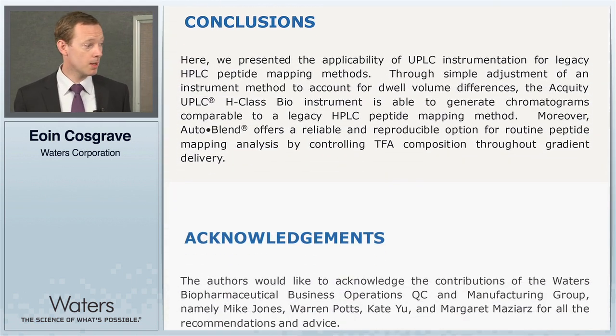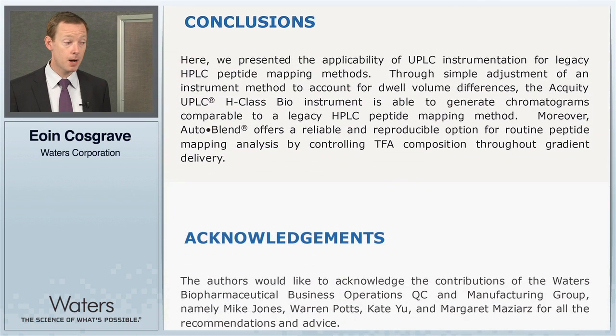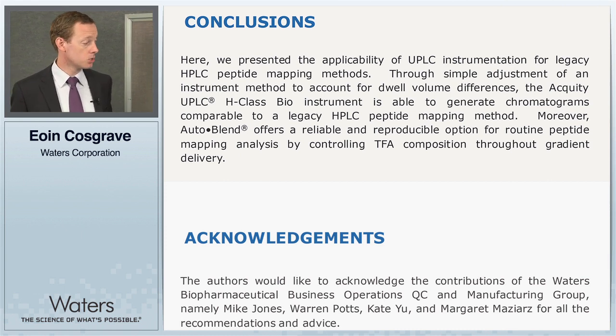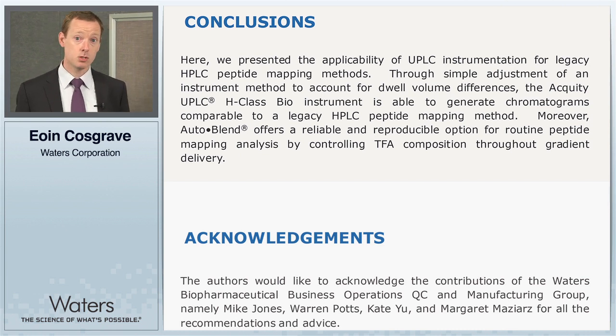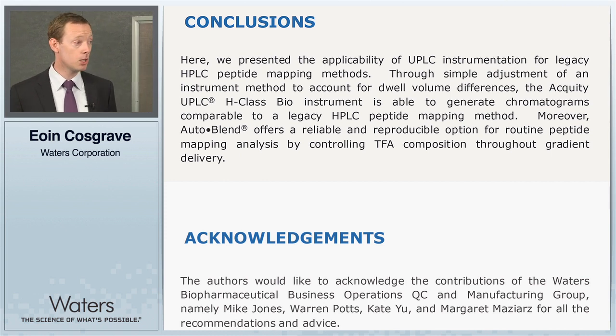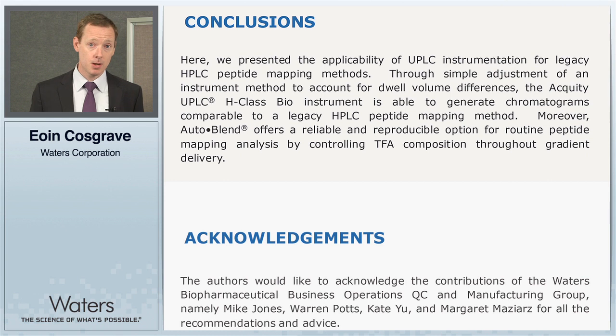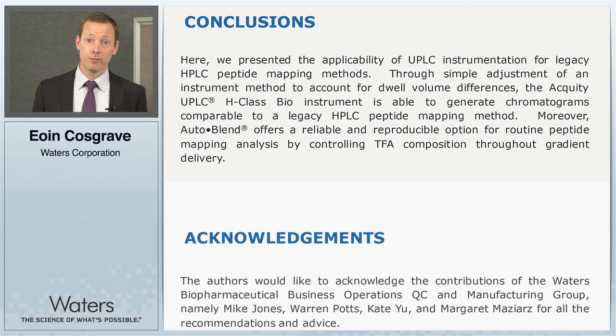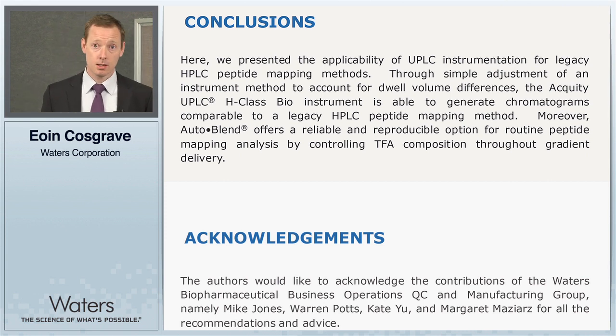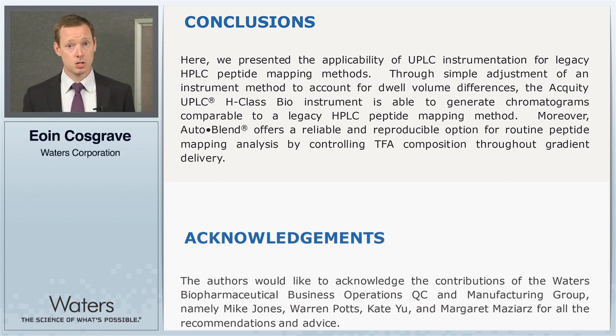In conclusion, we've demonstrated how we can use the Acquity H-class Bio for running legacy HPLC peptide mapping methods. By making a simple adjustment to the instrument method to account for differences in dwell volumes, we've achieved near-identical chromatography between two different instruments. Including an acidic modifier on a third solvent line with AutoBlend delivers precise, reproducible measurements. The H-class Bio is therefore a perfect instrument for both running HPLC legacy methods and transitioning into UPLC methods in the future. Thanks very much for your attention.